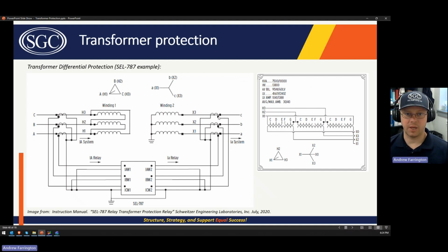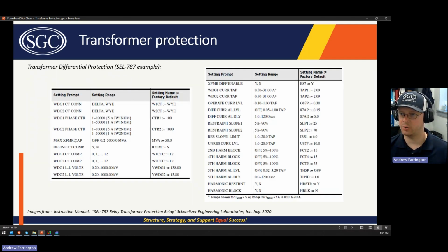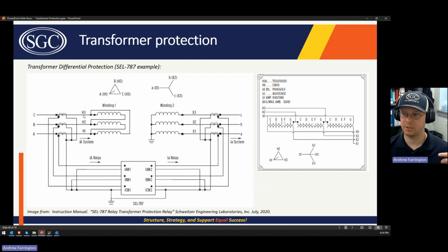If you don't account for that in your differential protection settings, then the relay is potentially going to trip for an out of section fault. We don't want that. So those are the two criteria as to whether or not you need to set this compensation setting to yes. So in both cases here, we have that phase shift. We have a source of zero sequence fault current within the zone of protection, so we need to set that to Y. It's also possible that you might have a grounding transformer within the zone of protection. That's less common. It's usually because you have a delta Y grounded transformer.